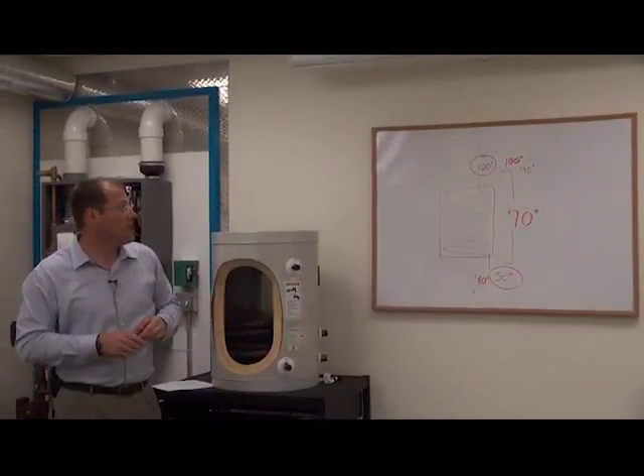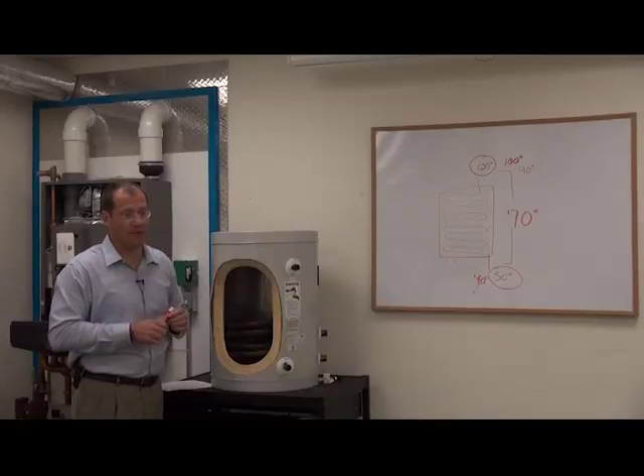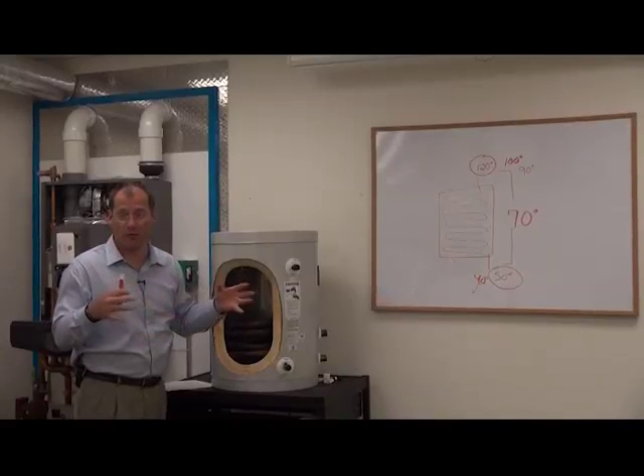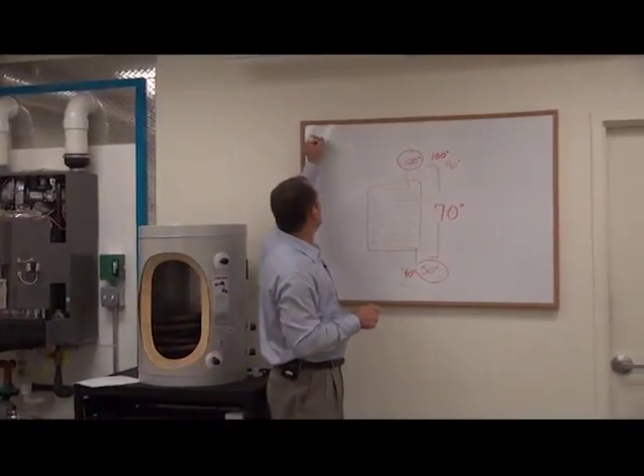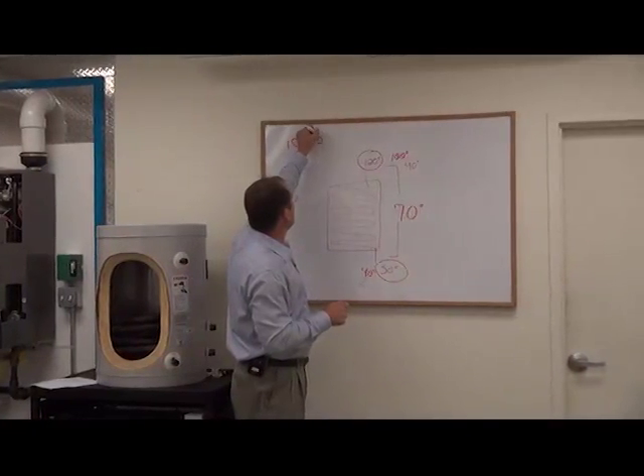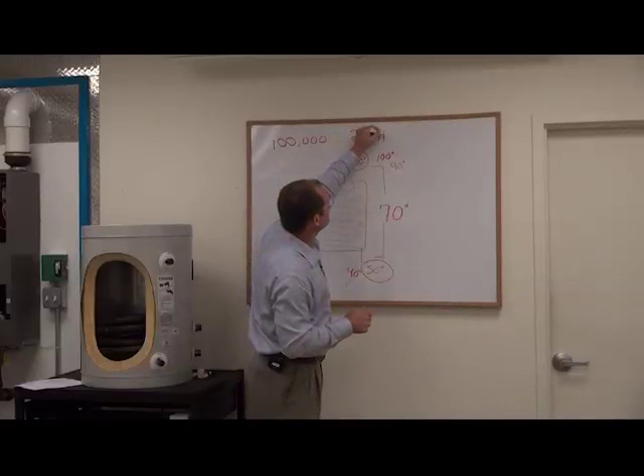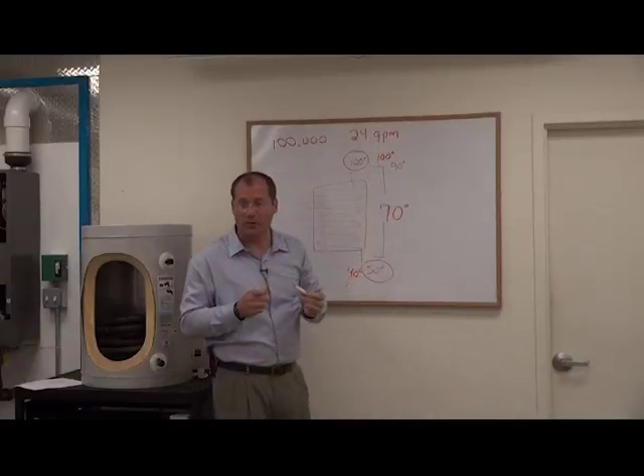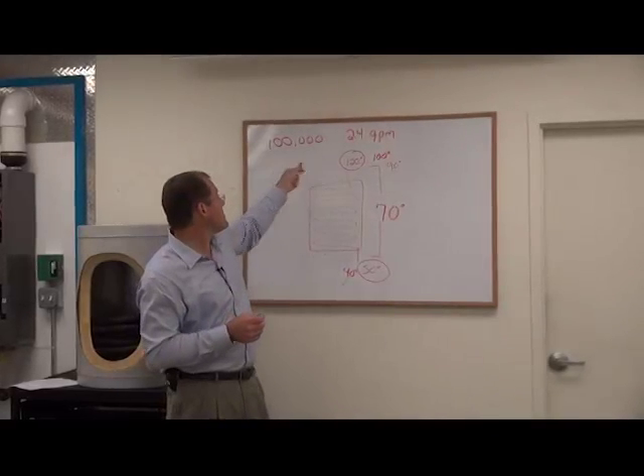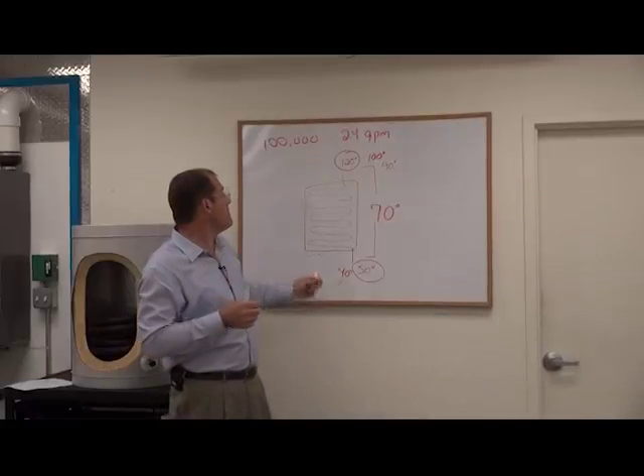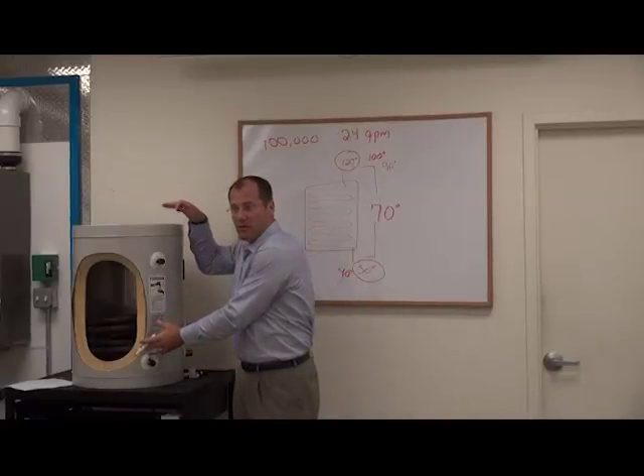The continuous flow through that unit is what? So when we size this equipment, people are sometimes thinking, why does it have to have so many BTUs, be so big? It's in order to produce, a 100,000 BTU unit will put out about 2.4 gallons a minute. That's one shower. That's one typical shower. So you're thinking, boy, my boiler for my house is 100,000 BTUs. You're telling me I need 100,000 BTUs just to have one shower running? And the answer is, in this application, yes, because you're not heating up and storing that big volume of water and then using it.